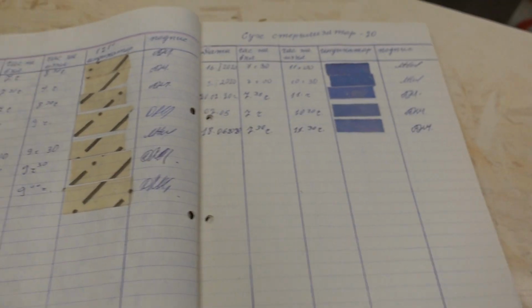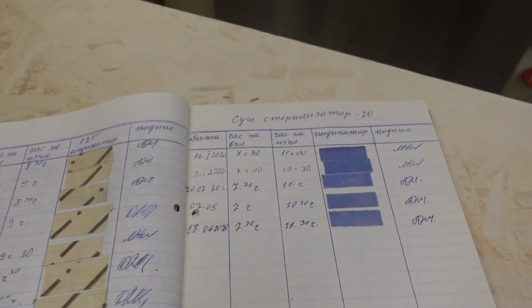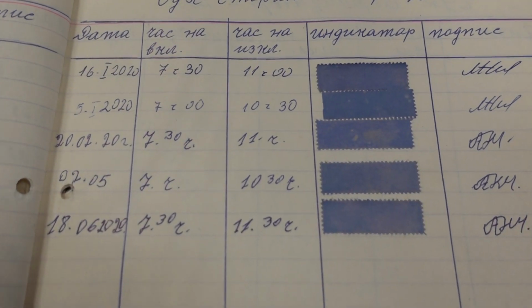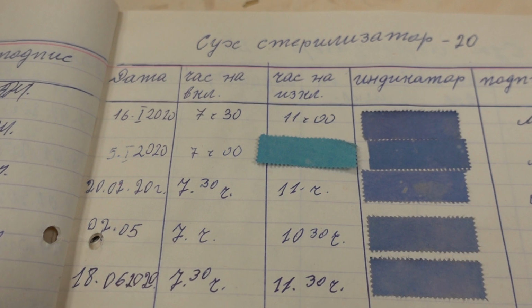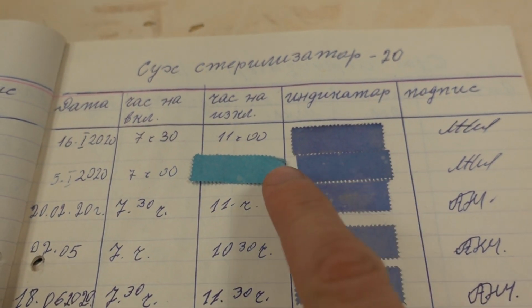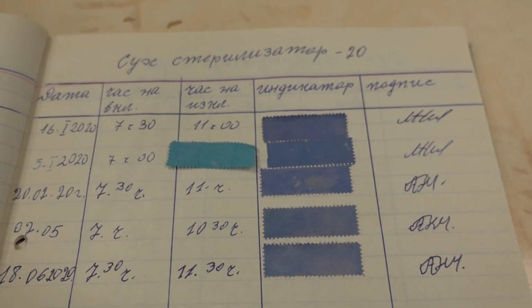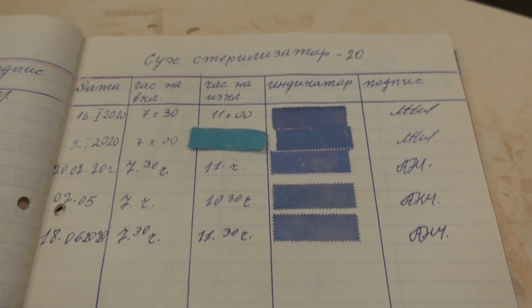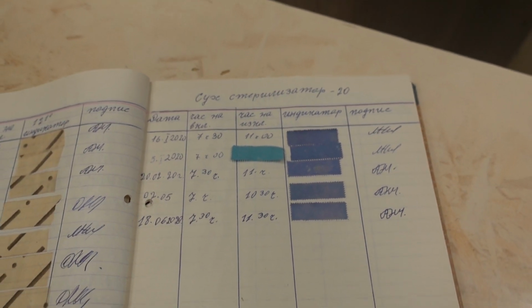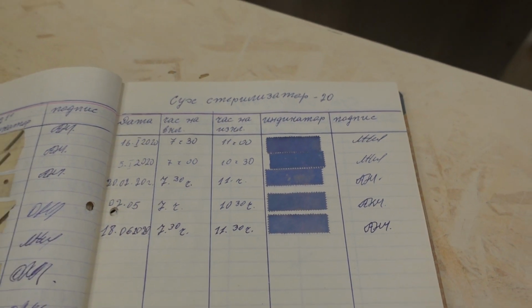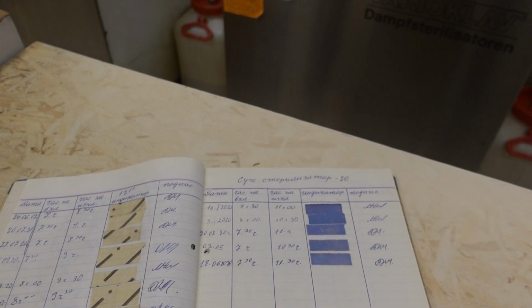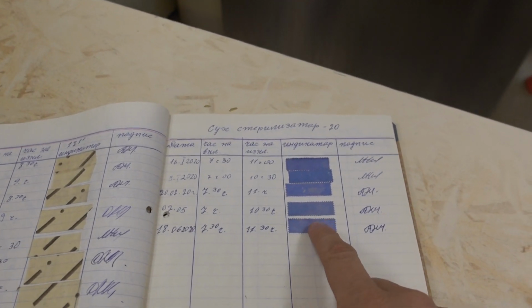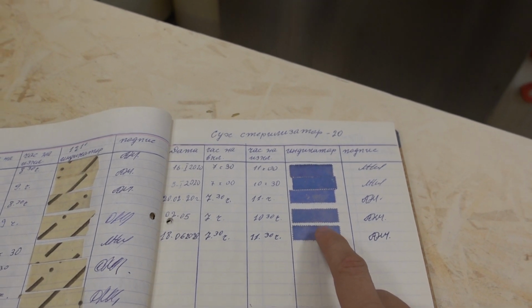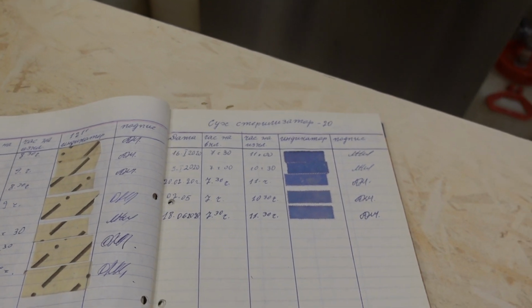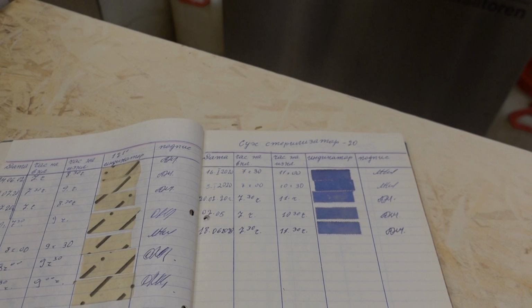Take a look here. This is our logbook. In the logbook, we write when the sterilization process started, when it ended, and do you see the difference? The way the paper changed its color. It turned into a deeper blue. That happens once the temperature reaches 160 degrees. So after that, the person who holds the sterilization process needs to sign and needs to stick the indicator paper inside. So this is a proof that everything was okay and the designated temperature was really reached and maintained.